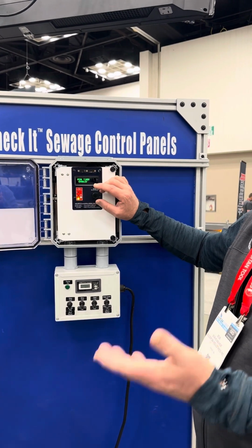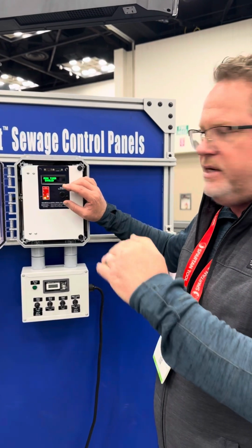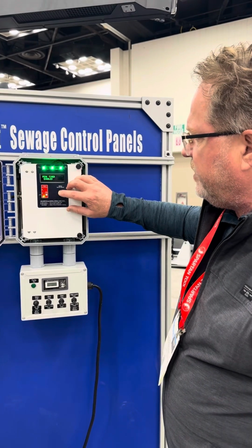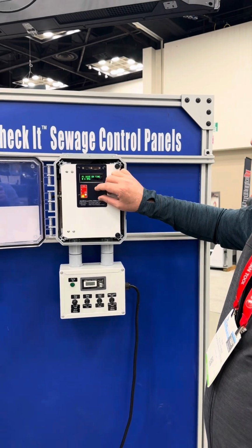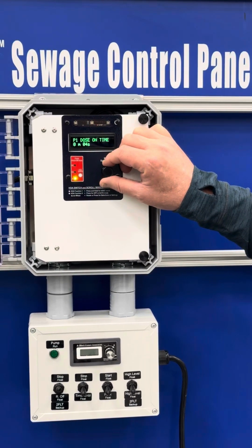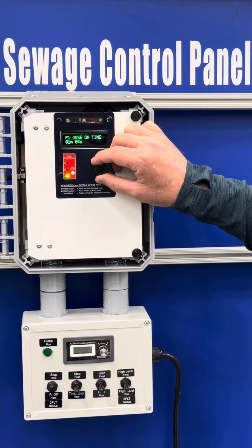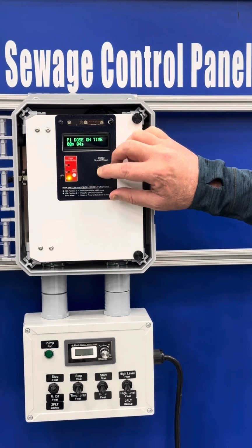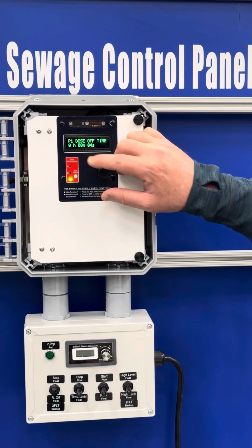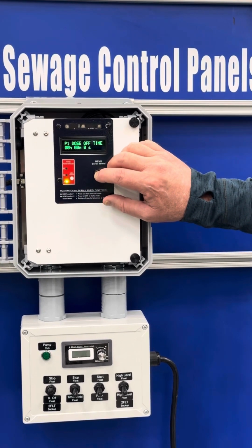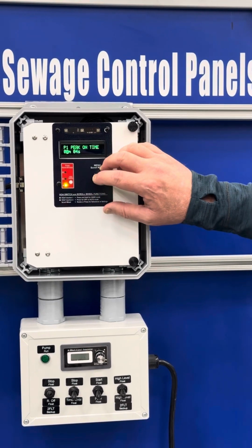And you can enable or disable the timer override or peak timer. So I'm going to keep it on for this demo. And here's your minutes and seconds that you program on. You know, typically 2-3 minutes or whatever the design engineer has calculated. But for our demo, I'll keep it at 4 seconds. Off time, hours, minutes, and seconds. My peak time settings.